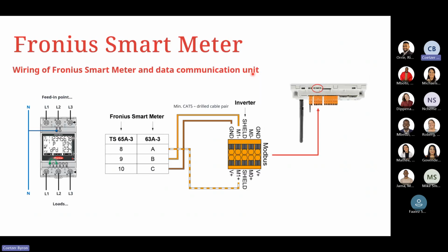Mentioning the Fronius smart meter, when you are doing the wiring of the meter itself coming in, we need to make sure that we're using M1 negative and M1 positive, as well as our grounding for the unit itself, and also the shielding, which is then back to the inverter itself. What you'll notice is we'll have a simple jumper between 7 and 8. This is referring to that terminator resistor that needs to be enabled, which will then be triggered by the terminator resistor DIP switches themselves.